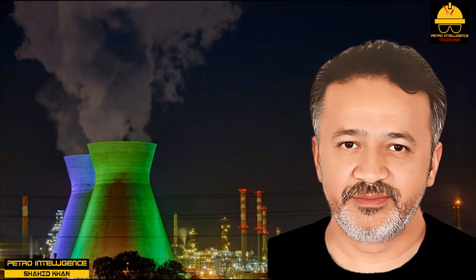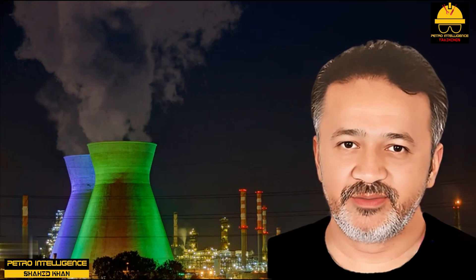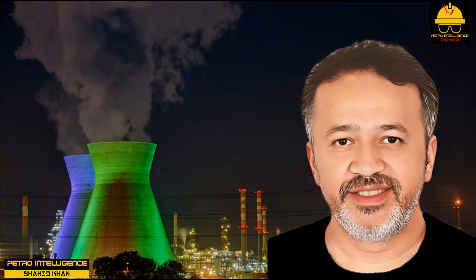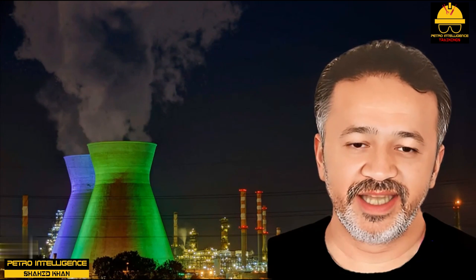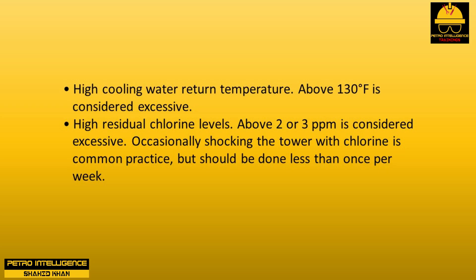Wooden cooling towers: most older cooling towers in the world are constructed of wood. The interior is filled with wooden slats; the lignin in these wooden slats is removed by the circulating water, causing the slats to break. Failure of the slats degrades air-water contacting, which raises the supply water temperature. The two things that accelerate lignin loss are: high cooling water return temperature — above 130°F is excessive — and high residual chlorine levels — above 2 or 3 ppm is excessive. Shocking the tower with chlorine should be done less than once per week.